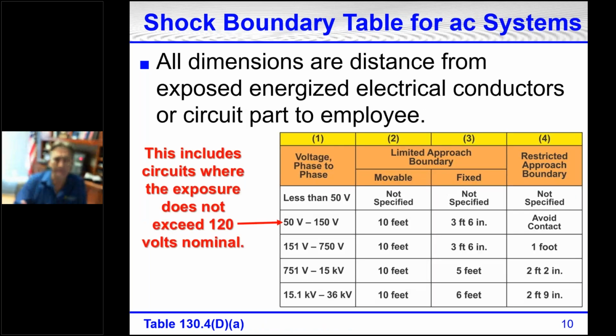All right, here's a little table that's based on table 130.4 D A. All dimensions are the distances from exposed energized electrical conductors or circuit parts to the employee. You'll see less than 50 volts, unless there's some other potential problem, this is AC, is going to be not harmful. So in other words, for the limited approach boundary, movable and fixed, there's no distance specified. For the restricted approach boundary for less than 50 volts, there is no distance specified.